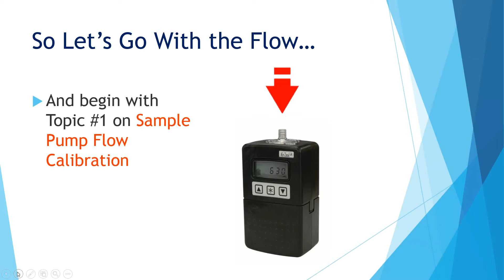Now, as most of you know, I have been with SKC a very long time, 32 years to be exact. And throughout those years, I've occasionally received phone calls from folks brand new to air sampling who are a bit confused that their new pump wasn't, quote, calibrated. And they questioned why they had to actually buy a calibrator. So here's a slide of clarification if you too are new to occupational hygiene sampling. When I say calibration of a pump, I mean that you set and verify the flow rate of the pump to that specified in the sampling and analytical method being followed. This is typically done before and after every sample that you take so that you can advise the lab of the air volume. Okay, so I want to be sure we're all up to speed on that.